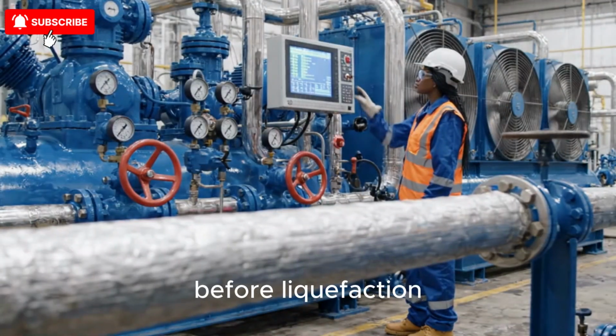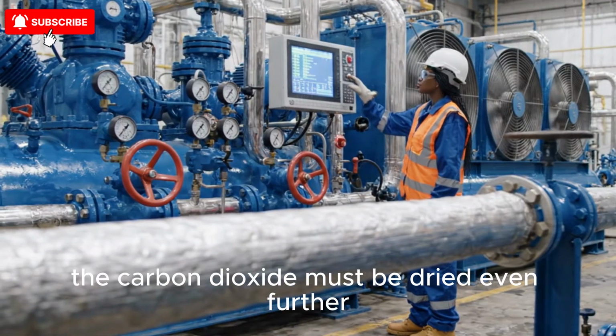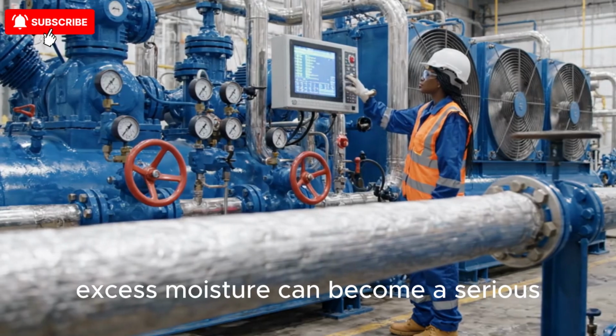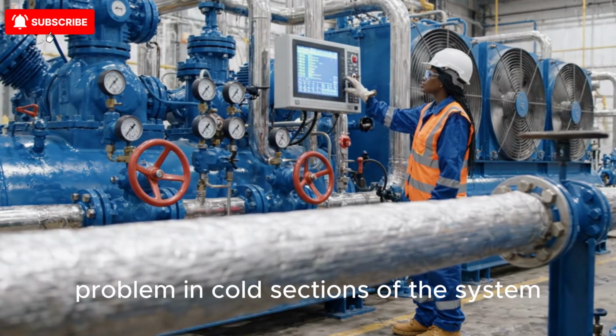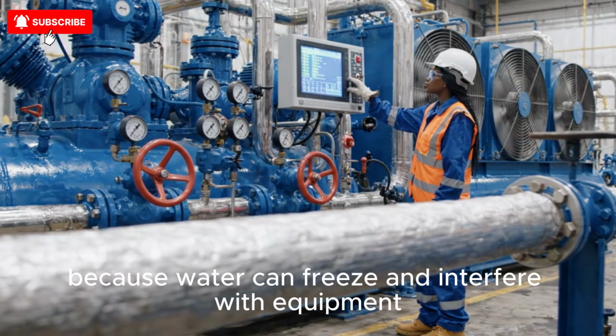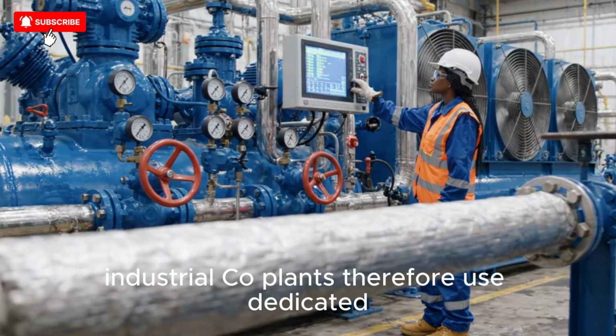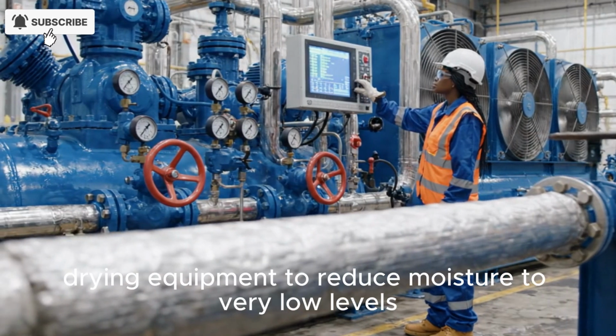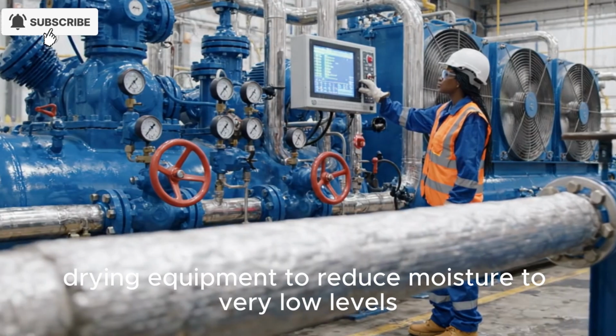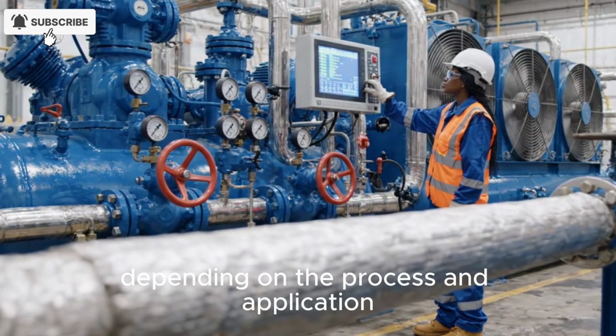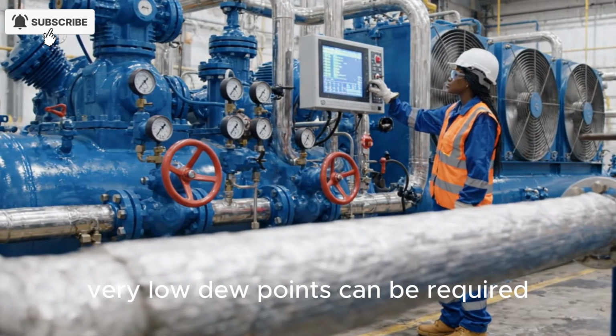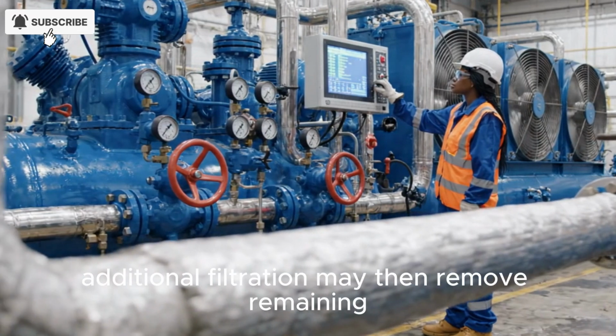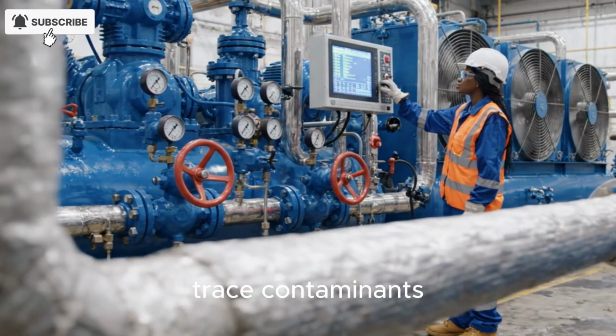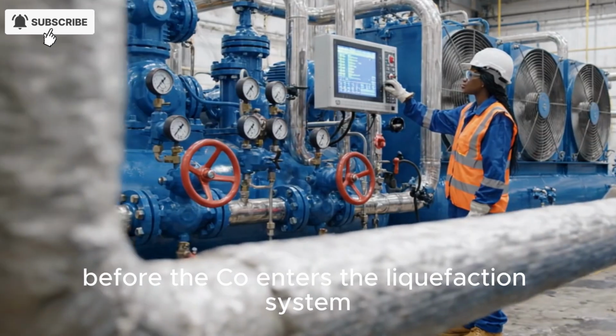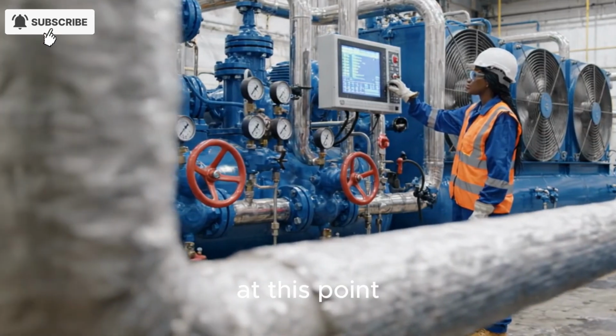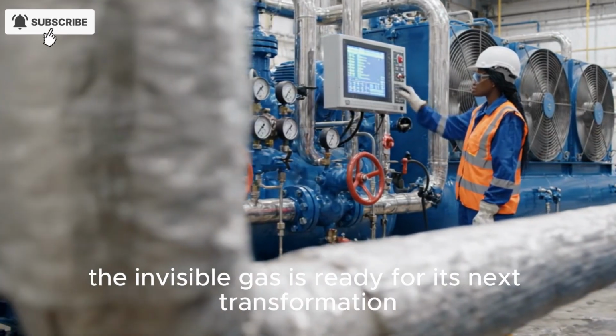Before liquefaction, the carbon dioxide must be dried even further. Excess moisture can become a serious problem in cold sections of the system because water can freeze and interfere with equipment. Industrial CO2 plants therefore use dedicated drying equipment to reduce moisture to very low levels. Depending on the process and application, very low dew points can be required. Additional filtration may then remove remaining trace contaminants before the CO2 enters the liquefaction system. At this point, the invisible gas is ready for its next transformation.